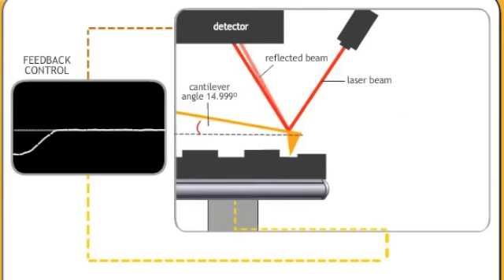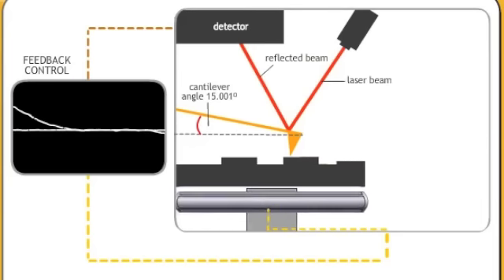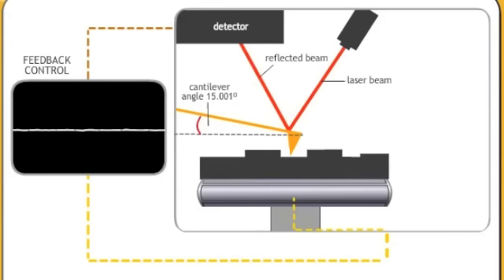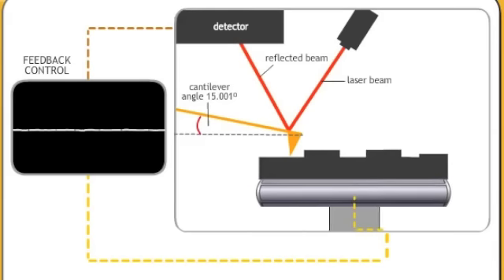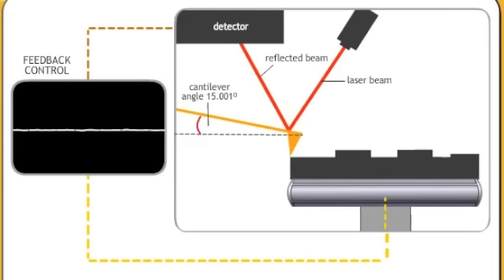The topography image is created from the path of the sample moving up and down while the deflection image is based on the deflection of the tip. The AFM operator adjusts the feedback control to minimize the deflection of the tip, increasing the accuracy of the topography image.